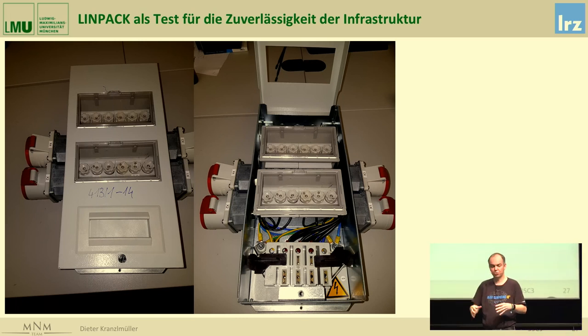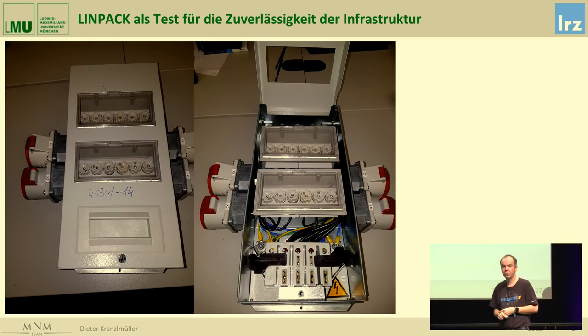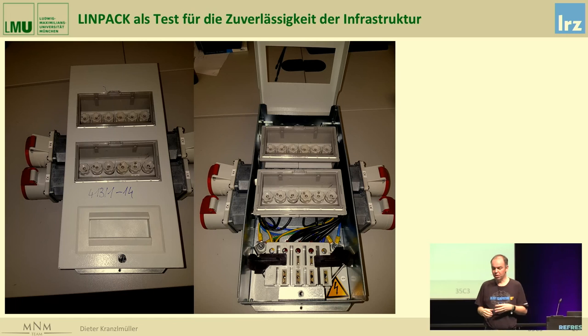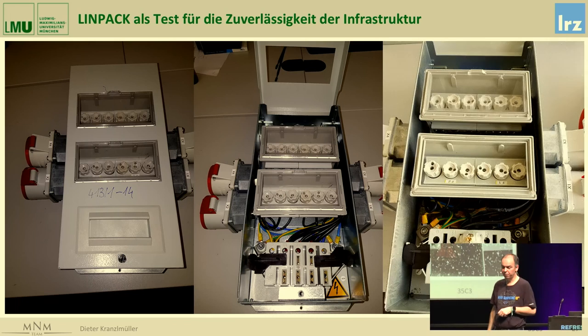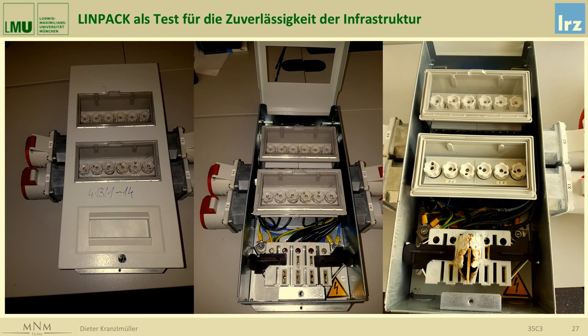On the other hand, Linpack is also a reliability test for the infrastructure. We see an output box with the fuses. You also see the two power connections to the left and the right - left the closed one, right the open one. What happened is that during one of these Linpack runs, the box looked like this - you see that the top of the lid has actually molten down by the heat that was produced in that box.